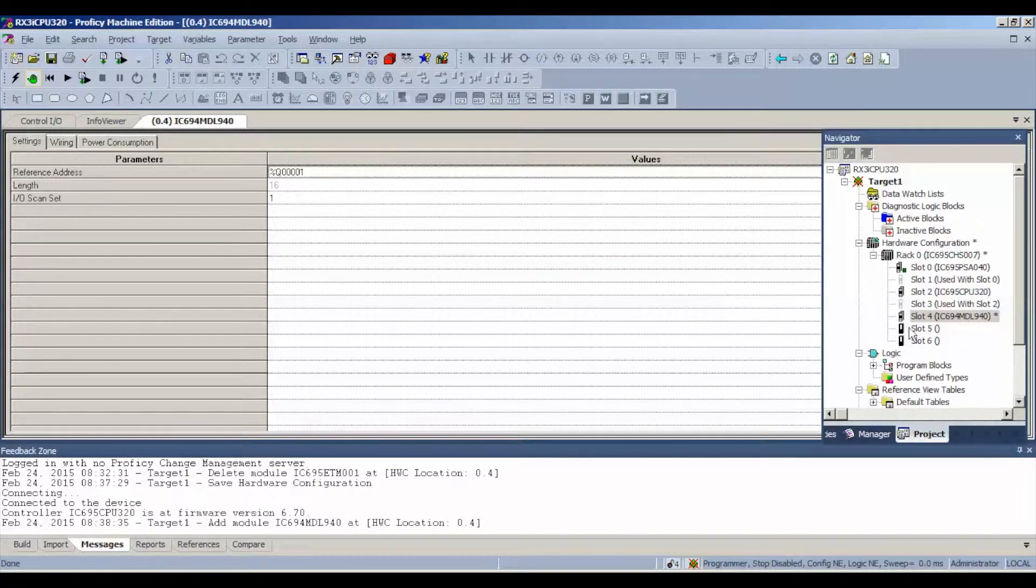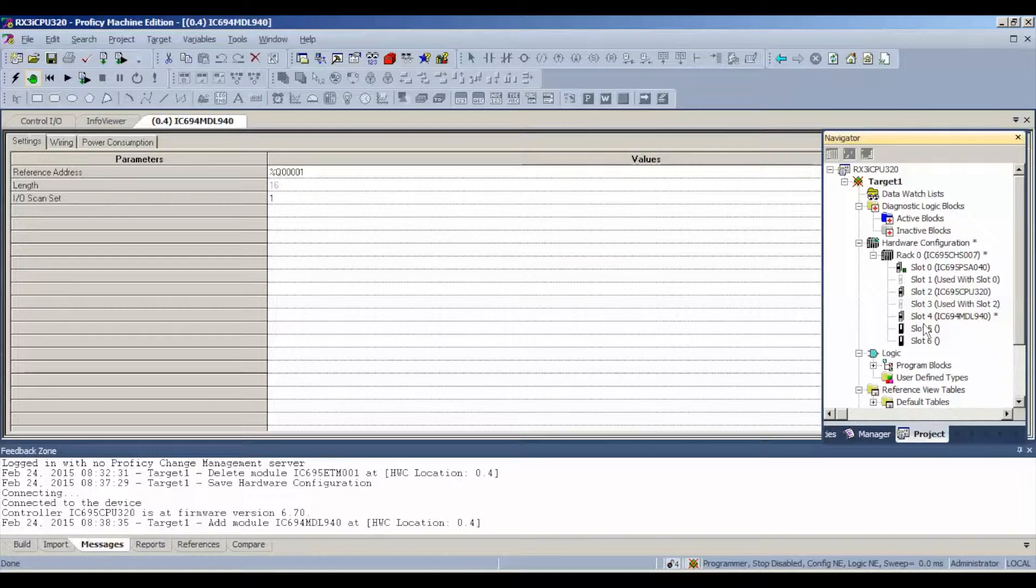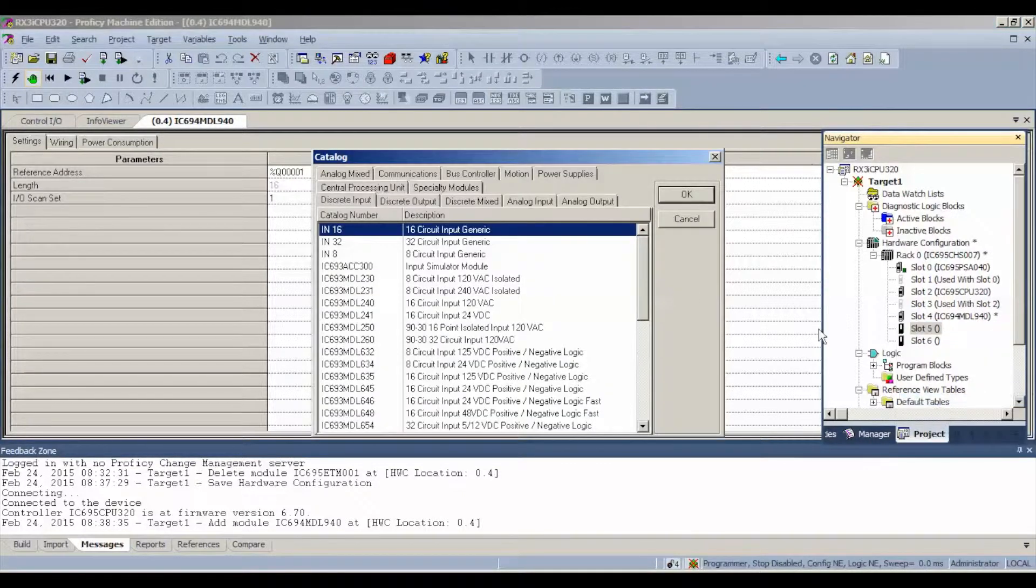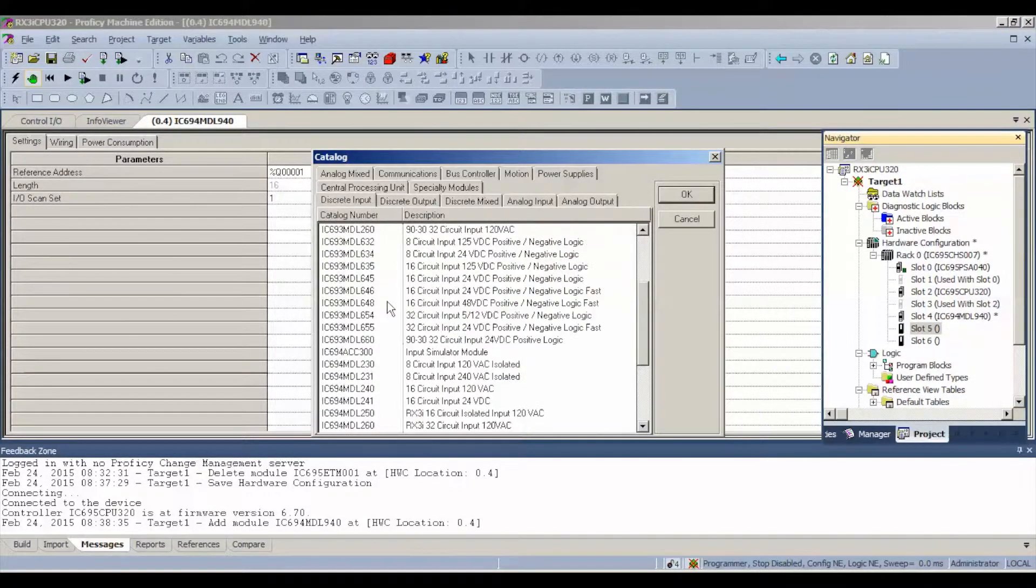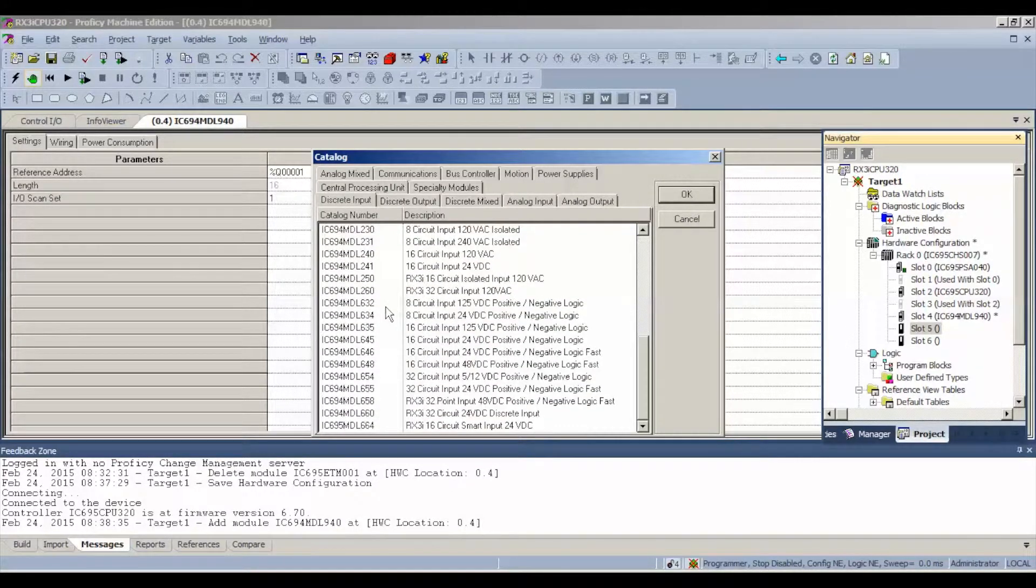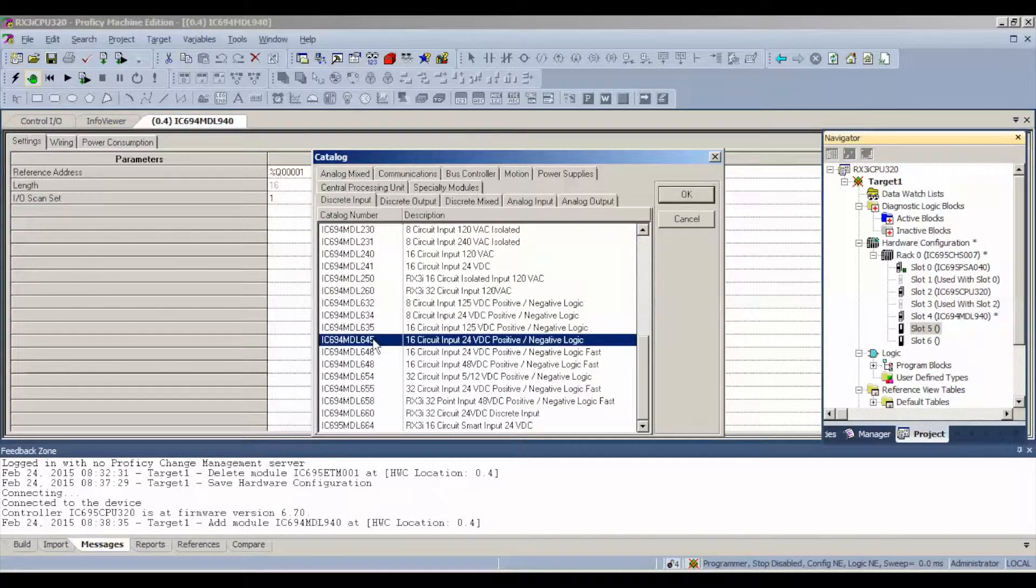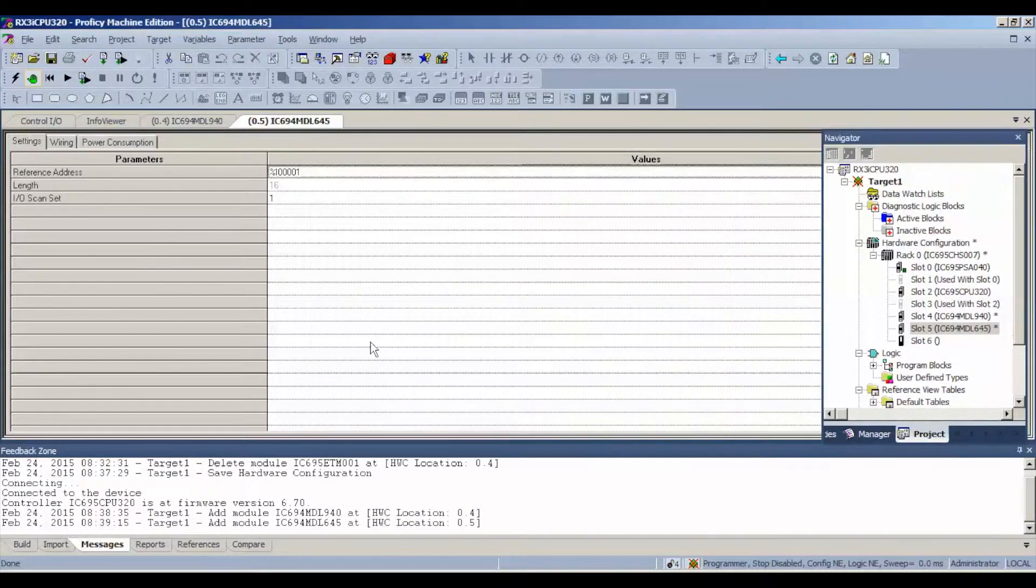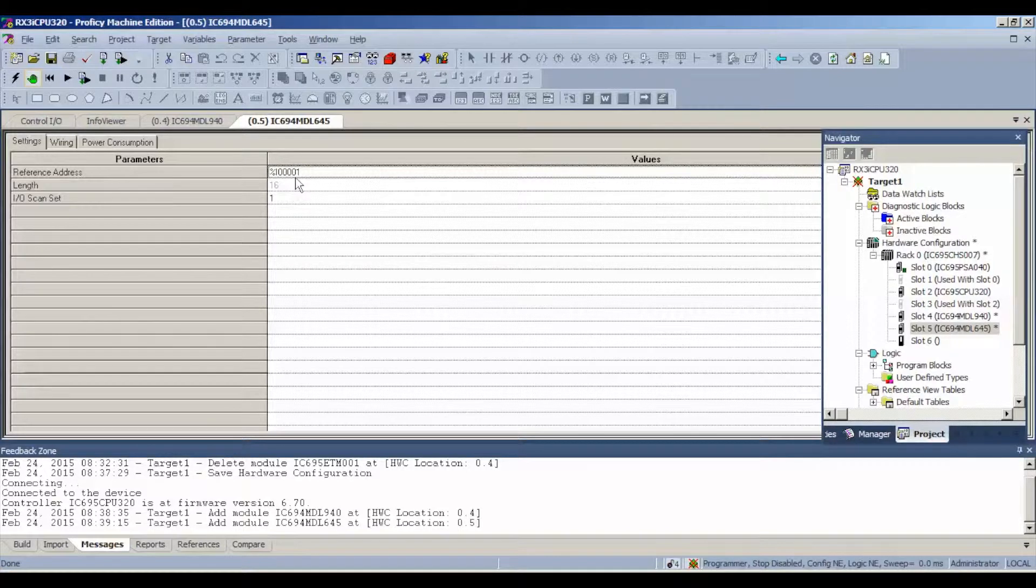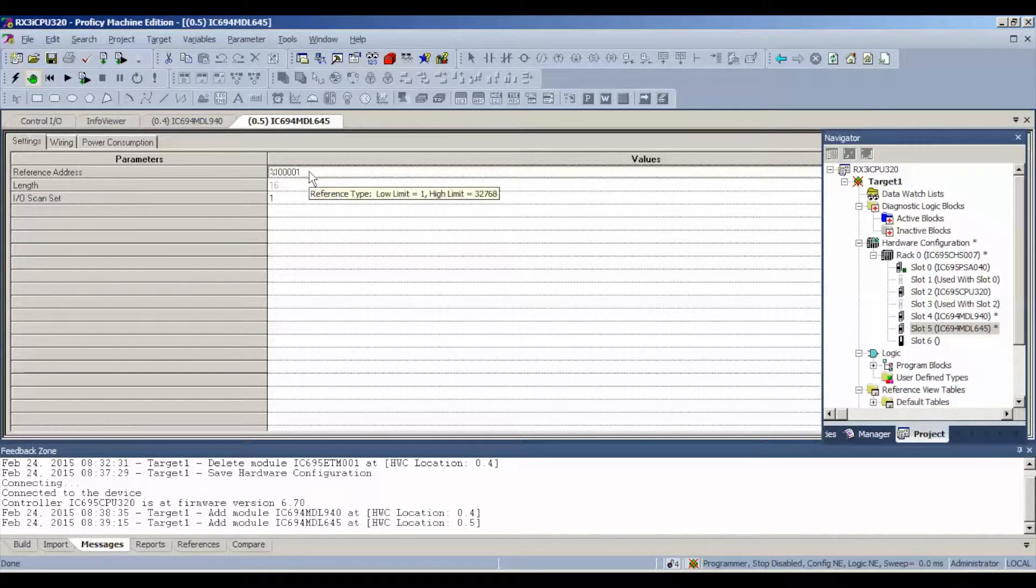Slot number 5, again right click or double click, add module, discrete input, IC694MDL645 or like I told you guys you can use a 646. Same thing, if you do want to see the reference address, if you want to see the inputs, just note that it's going to start on reference address number 1 on the input table.